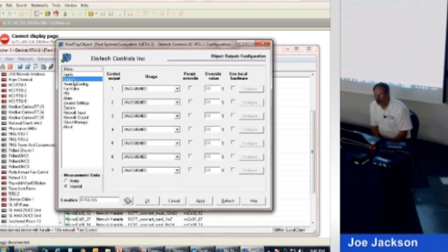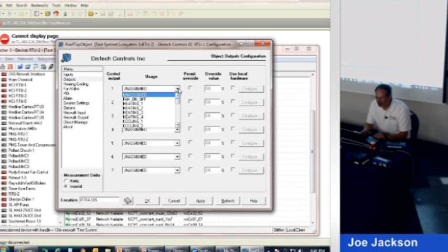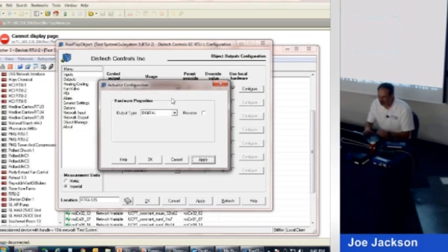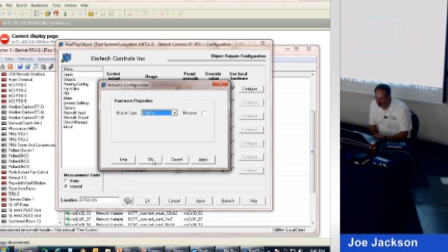Actuator. Well, I didn't give you guys enough information. So one thing that we have to turn on and off in a rooftop unit is the fan. So here's the fan. It's a digital output. That's really the only choice. It acts like it's going to give you another option, but a fan is either on or off. That's at least the fan state is. If you had a variable speed fan, we'll be able to see that later. But for now, we got the fan.